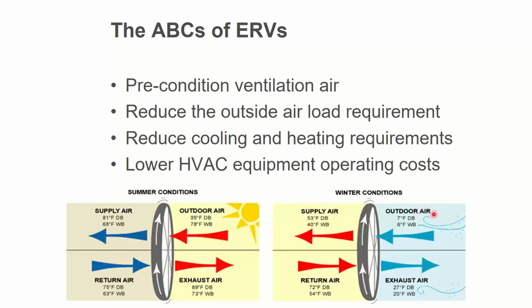So let's do a winter example first because it's easier to illustrate. Down in the bottom right, I got a 7-degree day, pulling cold, fresh air in from outside to meet ventilation code or just extra outside air, whatever it's going to be. I need fresh air. I bring it in at 7 degrees, right? Somewhere else in that space, I have return air, or I have exhaust air, you'd probably call it, that I'm going to throw away. Maybe it's from the toilet exhausts, maybe from somewhere else, but it's 72-degree conditioned air. I'm going to throw it out, exhaust it away.